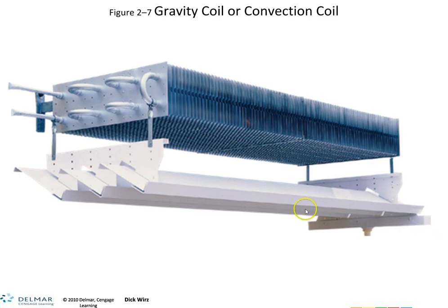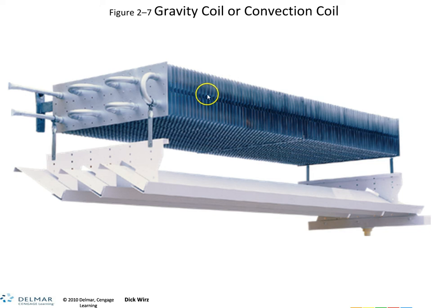A gravity or convection coil is a regular refrigeration coil for a cooler. You'll notice the fin spacing here is quite a bit wider than you're used to seeing. There's no fan whatsoever — the coil begins to cool down, cold air falls down into the cooler. The condensation pans here catch the drip when the coil starts to drip, and drain it out. You don't see these very often.